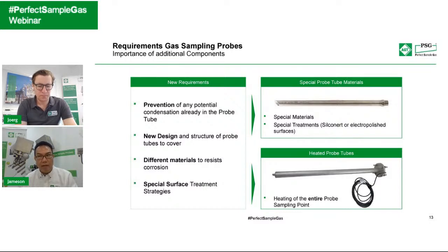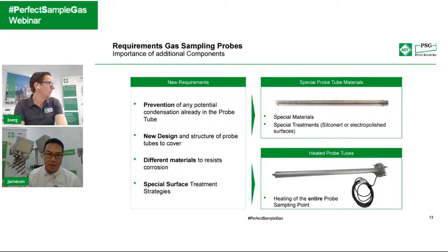The purpose of the heated sample tube is to separate water and particles. During the journey in the heated sample tube, the water and the sticky dust only stick because they are together. We want to separate them so that the maintenance interval between service is much longer. So this is my answer: choose a heated sample pipe instead of a PTFE sample tube.